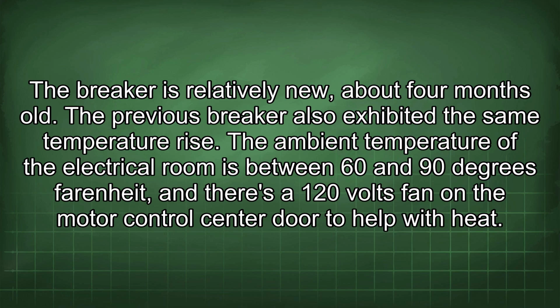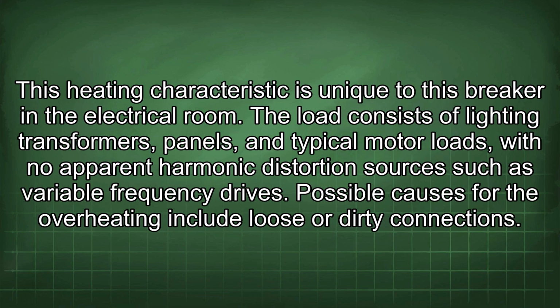The ambient temperature of the electrical room is between 60 and 90 degrees Fahrenheit, and there's a 120 volt fan on the motor control center door to help with heat. This heating characteristic is unique to this breaker in the electrical room. The load consists of lighting transformers, panels, and typical motor loads, with no apparent harmonic distortion sources such as variable frequency drives. Possible causes for the overheating include loose or dirty connections.